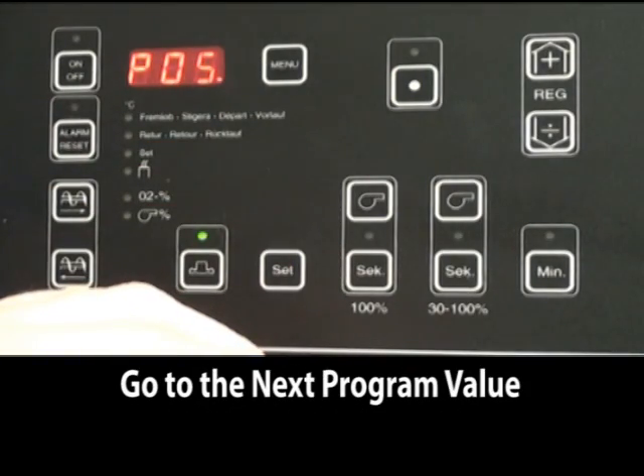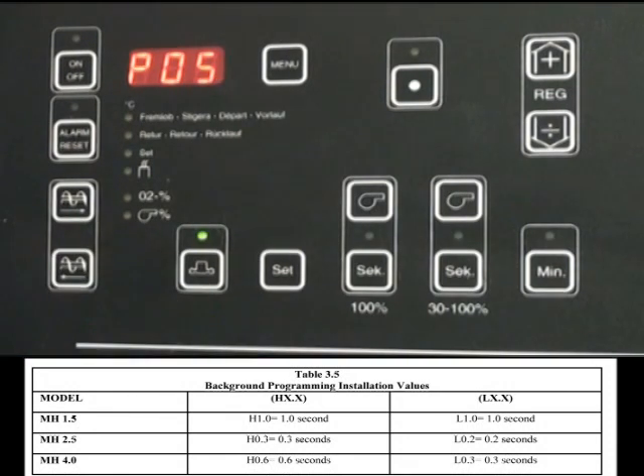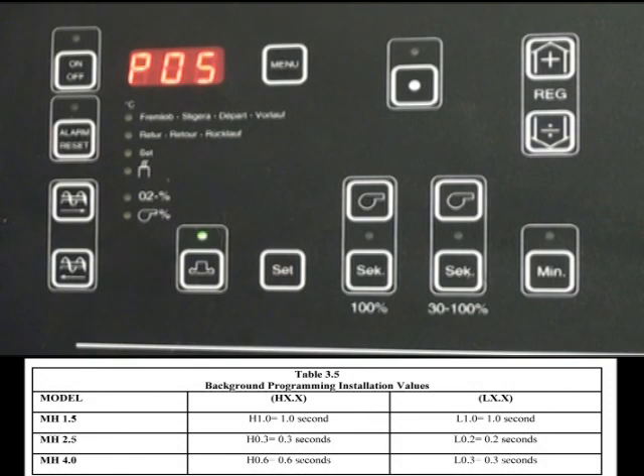Next setting is the blower running time in seconds in standby mode or min mode. It should be defaulted to P05 or 5 seconds. It must be left at this setting.